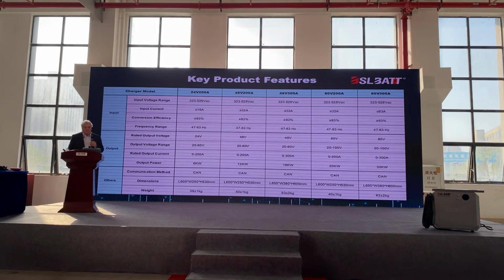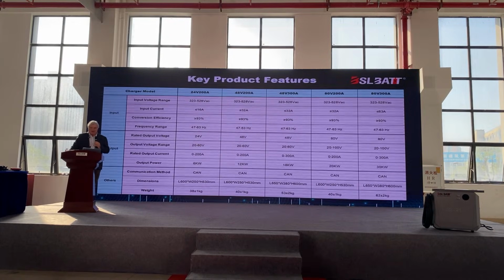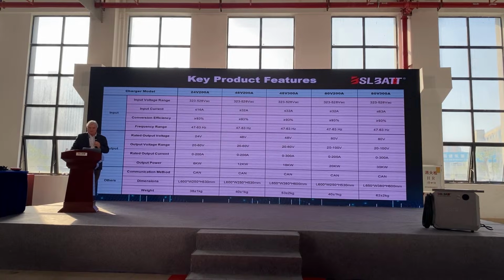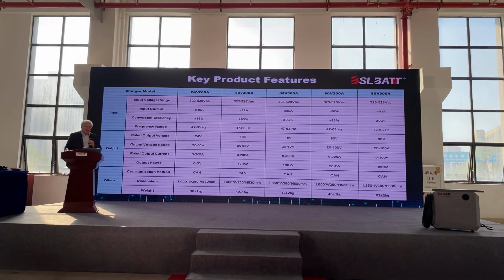Some key product features: it's a 93% efficiency conversion charger, running at a very high level. The voltages are 24 through 80 volts, with 200 to 300 amp output depending on the voltage and application. All CAN communicated for our batteries for optimum protection.